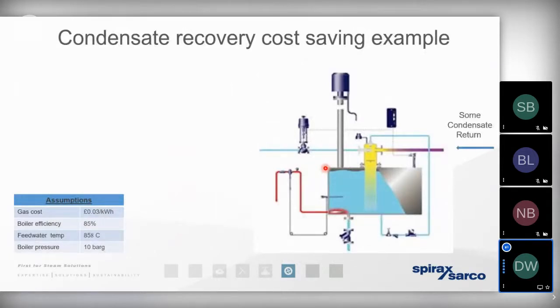So if we use an example where we know that gas costs, say, 3 pence per kilowatt hour, and if we know the boiler's badged with an efficiency of 85%, if the steam boiler pressure is 10 bar gauge, and if the temperature of the feed tank or the hot well is 85 degrees, well, we might mistakenly assume that because the temperature of the hot well is 85 degrees, that means that we've got an excellent rate of condensate return.